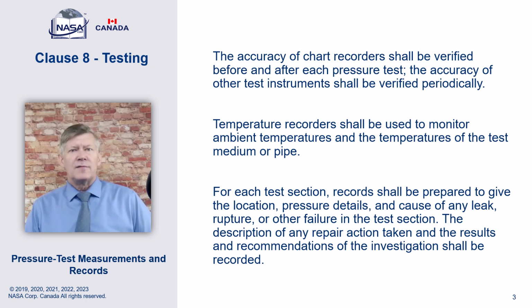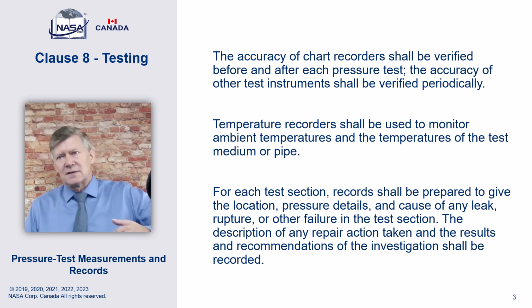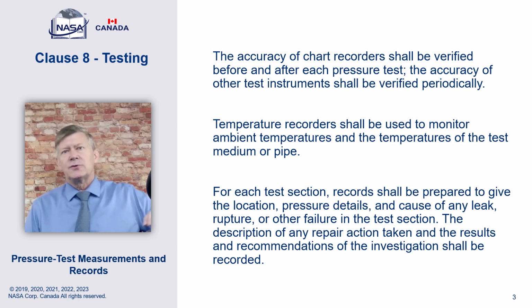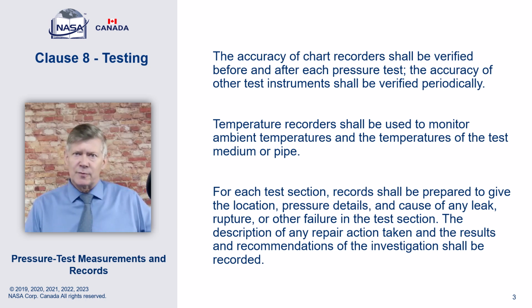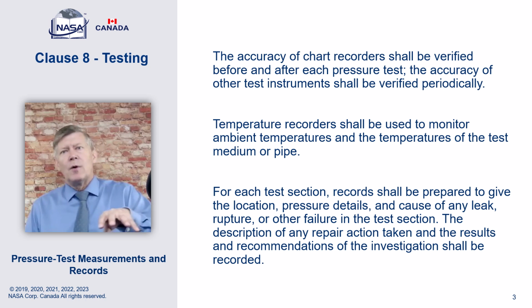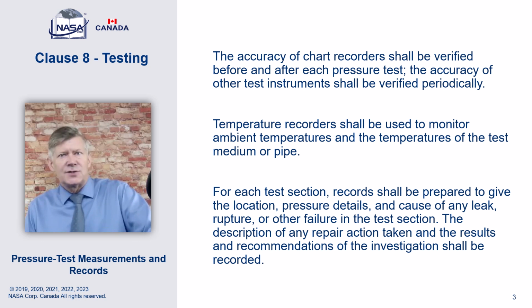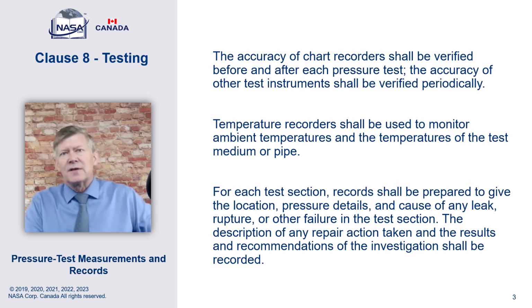Okay, we're saying verified. And the difference between calibrated and verified, calibrated is conducted by an accredited calibration laboratory. It's documented. It has a report that's traceable to a national standard. The report will identify the condition the equipment was received in prior to calibration, what was done for the calibration, and a certificate that it is now calibrated and reading accurately. Okay, verification, the process is very, very similar, if not the same as calibration. The difference is it's something that we can do.